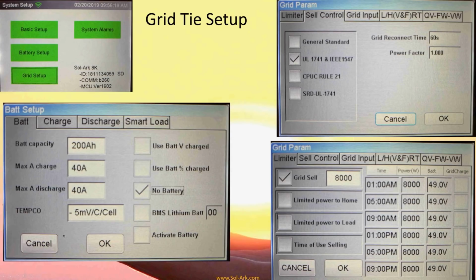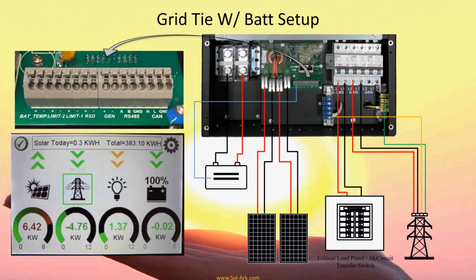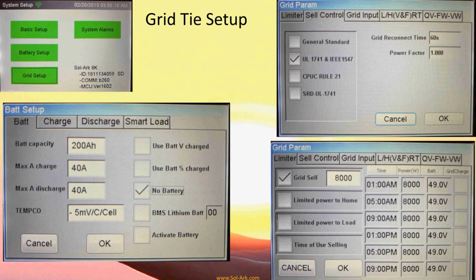So we'll select no battery. UL 1741 is the default under grid parameters, grid setup, and normally it's limited power to load for safety, so we'll select grid sell and click OK. We have to click OK in every tab setting because it's a safety feature - we want to make sure you wanted to program it that way exactly. And that is basically how we set it up for grid tie setup. It's very, very simple, not a lot to it.